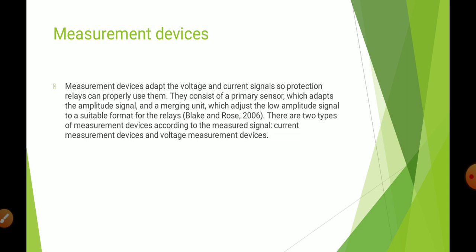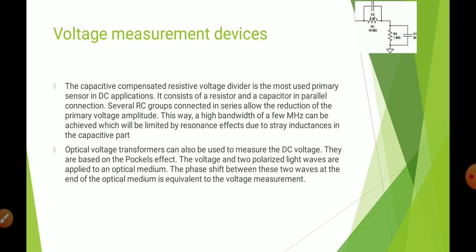Measurement devices. The measurement devices adapt the voltage and current signals so protection relays can properly use them. It consists of a primary sensor which adapts the amplitude signal and a merging unit to merge them, which adjusts the low amplitude signal to a suitable format for relays. There are two types of measurement devices to measure signal: current measurement devices and voltage measurement devices.